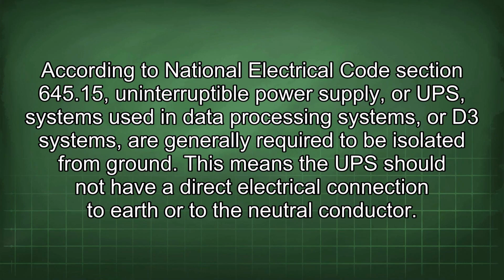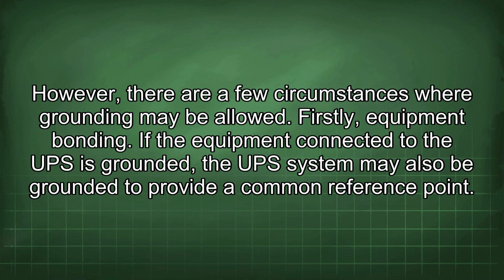According to National Electrical Code Section 645.15, uninterruptible power supply, or UPS, systems used in data processing systems, or D3 systems, are generally required to be isolated from ground. This means the UPS should not have a direct electrical connection to earth or to the neutral conductor. However, there are a few circumstances where grounding may be allowed.